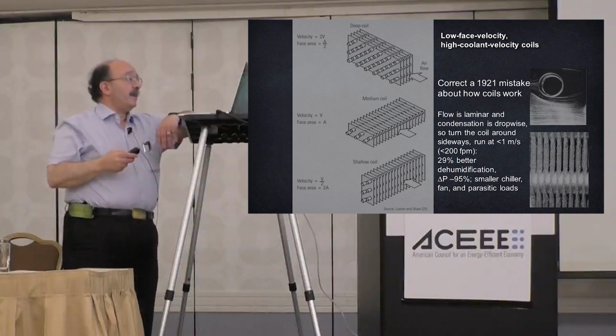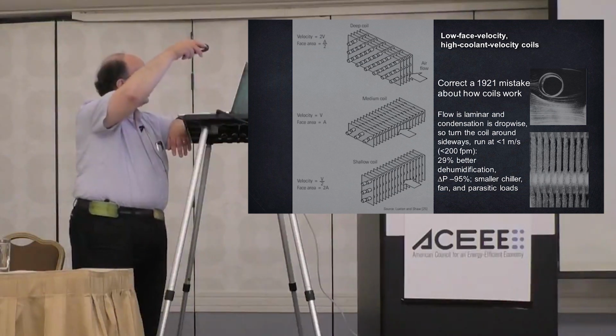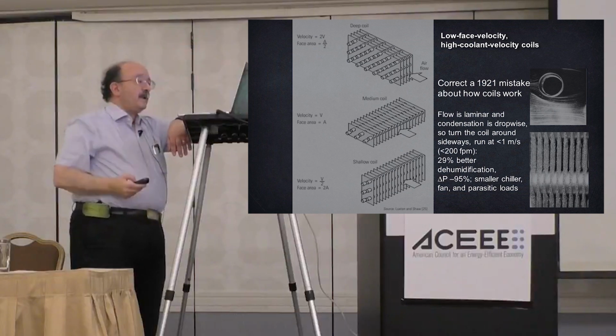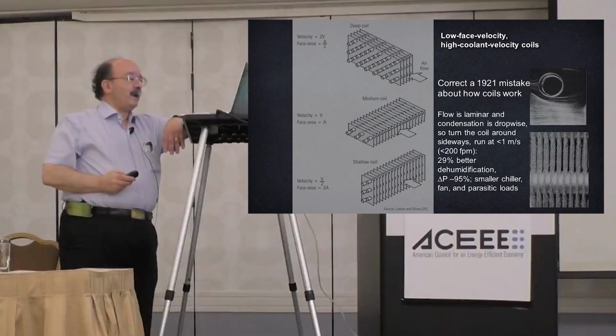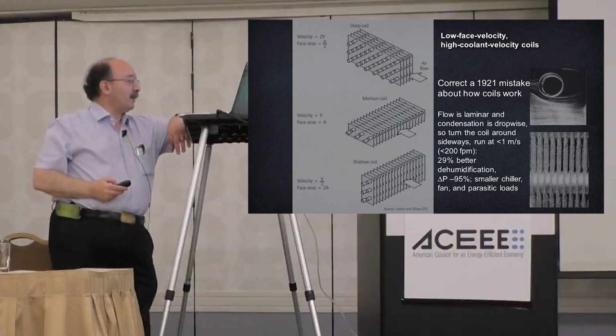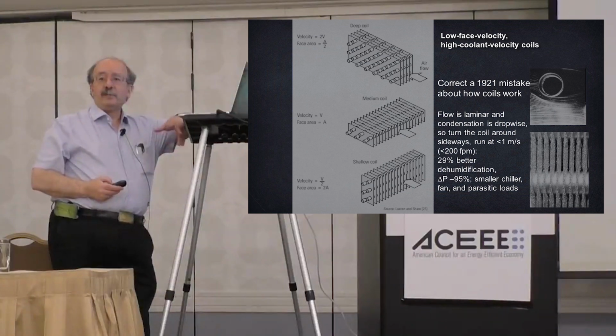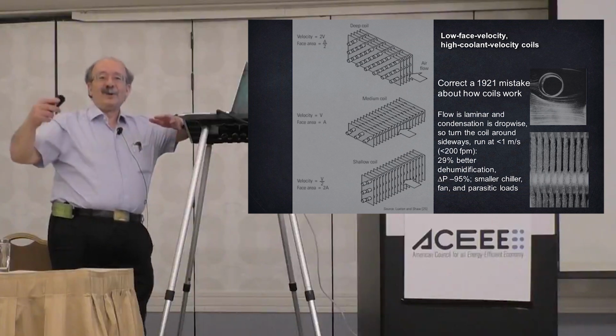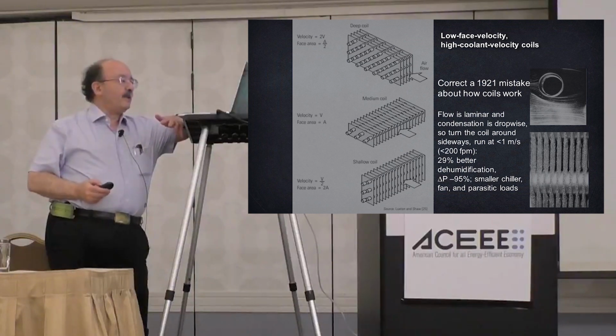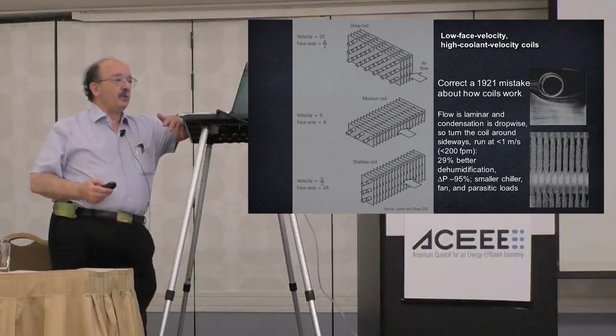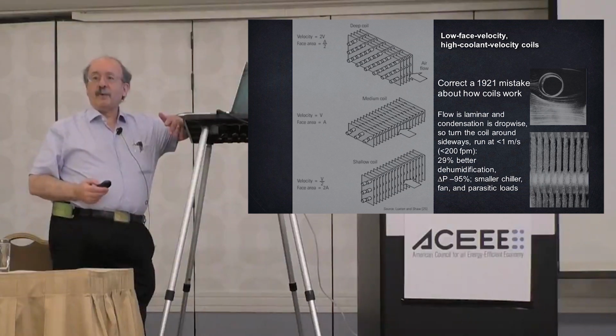So if you turn the usual deep, dense coils sideways and blow the same fast flow of air through the same mass of copper at a quarter of the face velocity—keeping the face velocity under a meter per second, under 200 fpm—then you preserve those droplets and their extra surface area. You get 29% more dehumidification per unit of sensible cooling, the airside pressure drop goes down by a factor of 20, the fan gets smaller, the evaporator load shrinks, and the whole cooling system shrinks.